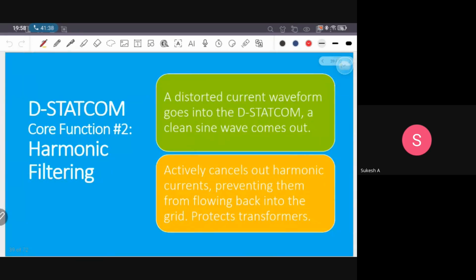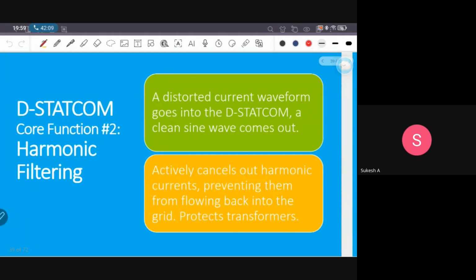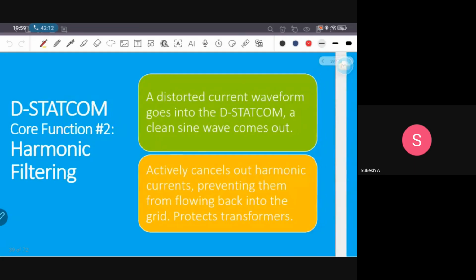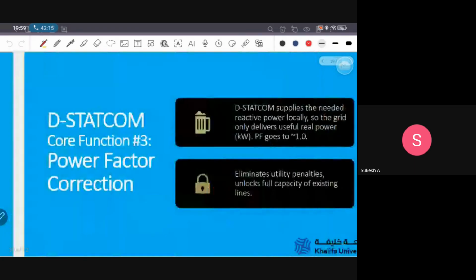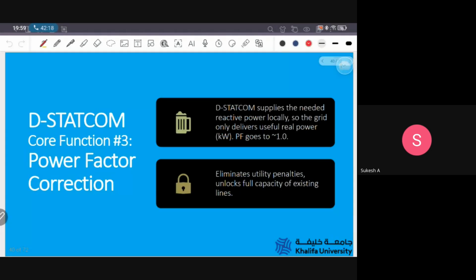Its other core function is harmonic filtering. It acts as an active filter. It measures the distorted load current from the charger output. If it is not a sinusoidal waveform, it has to make the grid current sinusoidal. So the remaining waveform, the harmonics, is supplied from our DSTATCOM or our inverter. Finally, we are making the grid current sinusoidal and reducing the harmonics and all the issues with harmonics, such as overheating and burnout of transformers.